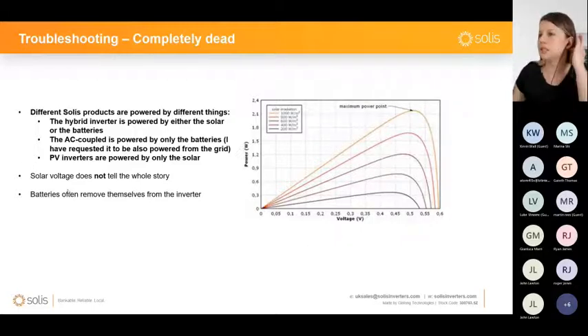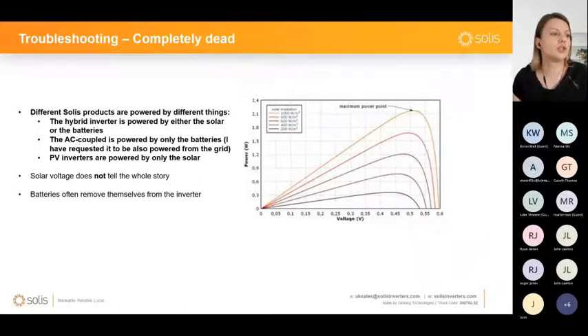Yeah, and as I said here, solar voltage does not tell the whole story. Sometimes you might have voltage, but if the system has a startup voltage of 120 and you are measuring an open circuit voltage of, I don't know, 130, keep in mind that that's just open circuit. When you're connecting it to the inverter, the PV string will drop. It's going to have a voltage drop on the string, and it might not be enough to start the inverter. You might have to wait for a sunny day, or you might have to check the string. It might be that you have a faulty panel that is now not allowing your string to get to that voltage you need.